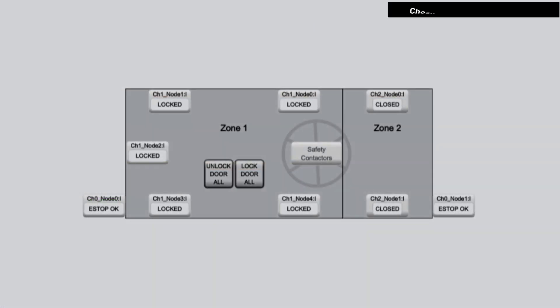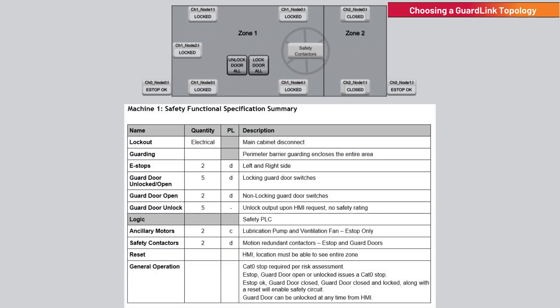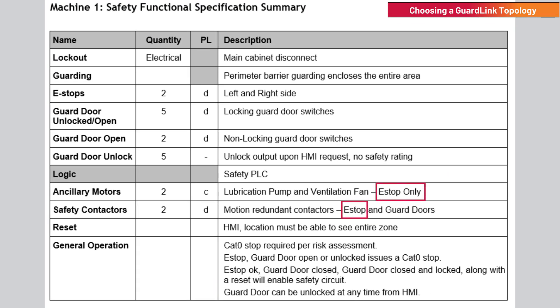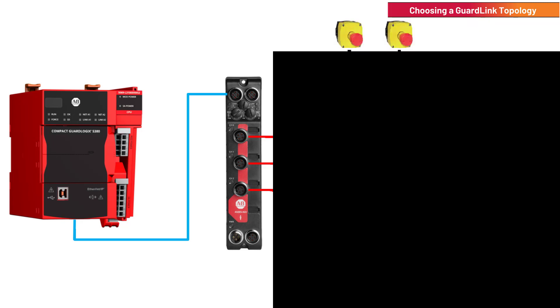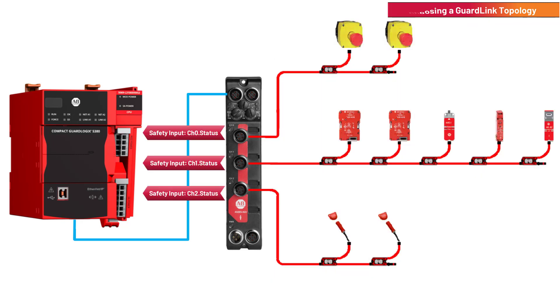Some safety system designs require reacting differently to different types of inputs. For example, if all power is required to be shut down on an emergency stop, but only motion power is required to be shut down during a guard door open, then e-stops would need to be on a GuardLink channel separate from guard doors. The example program separates e-stops, locking guard doors, and non-locking guard doors.